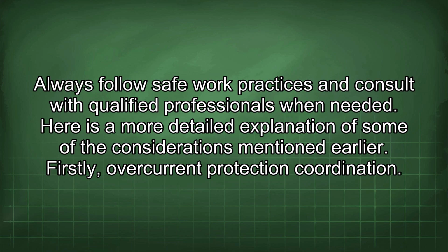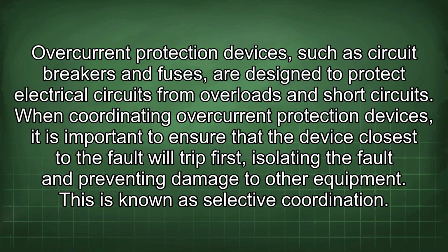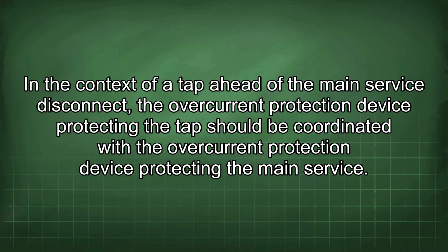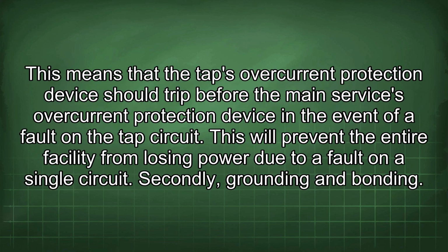Firstly, overcurrent protection coordination. Overcurrent protection devices, such as circuit breakers and fuses, are designed to protect electrical circuits from overloads and short circuits. When coordinating overcurrent protection devices, it is important to ensure that the device closest to the fault will trip first, isolating the fault and preventing damage to other equipment. This is known as selective coordination. In the context of a tap ahead of the main service disconnect, the overcurrent protection device protecting the tap should be coordinated with the overcurrent protection device protecting the main service. This means that the tap's overcurrent protection device should trip before the main service's overcurrent protection device in the event of a fault on the tap circuit. This will prevent the entire facility from losing power due to a fault on a single circuit.